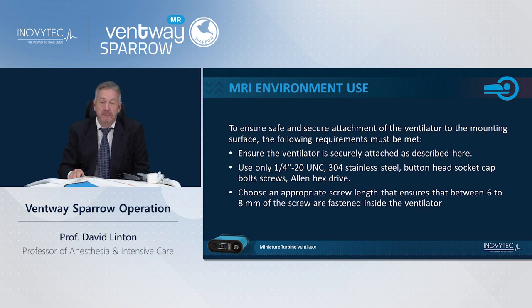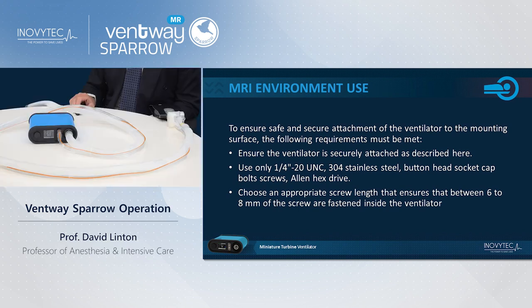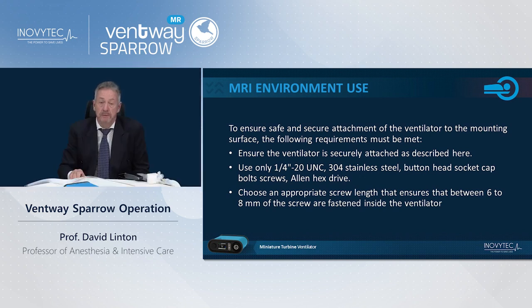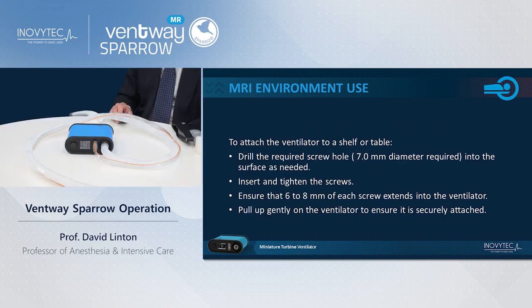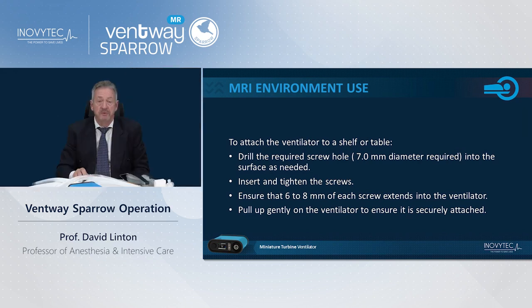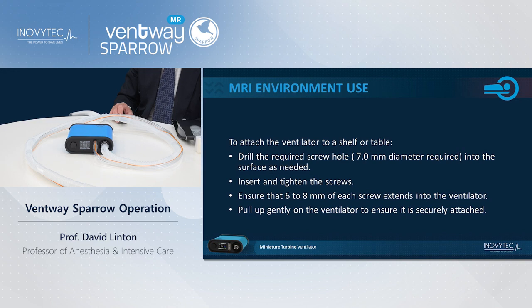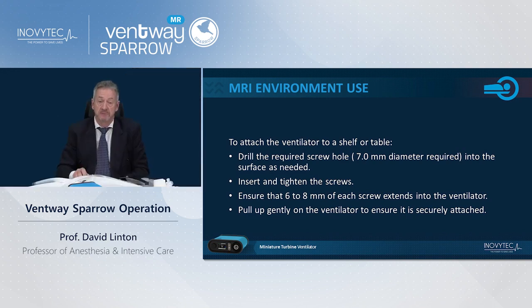It must be safely secured using 1/4 inch stainless steel button head socket cap bolt screws and an Allen hex drive. Choose an appropriate screw length that ensures that between 6 to 8 millimeters of the screw are fastened inside the ventilator. So to attach the ventilator to the shelf or table in the MRI environment, you must drill the required screw hole 7 millimeters in diameter into the surface on which it's going to be mounted. Insert and tighten the screws as described on the previous slide, and ensure that 6 to 8 millimeters of each screw extends into the ventilator to keep it secure.